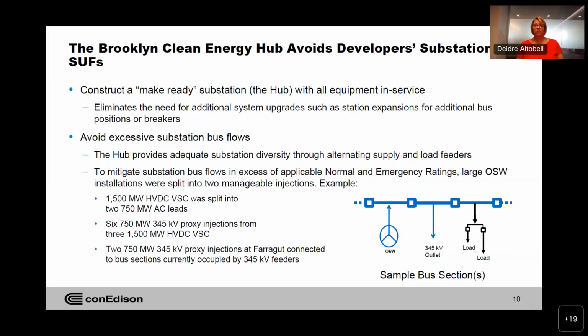This will mitigate bus flows so that the flows throughout the station do not exceed normal or emergency ratings of the station equipment. Similarly, at neighboring Farragut, a single large injection would be split into 2 smaller proxy injections to ensure that local station equipment ratings are not violated. This means that 2 lines will bring a 1,500 megawatt injection from the inverter to the point of interconnection. To reiterate, the Brooklyn hub is designed to maintain reliability inside the station, thus avoiding SUFs for the developer.